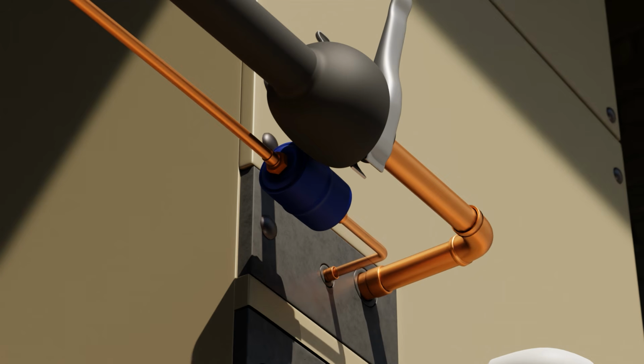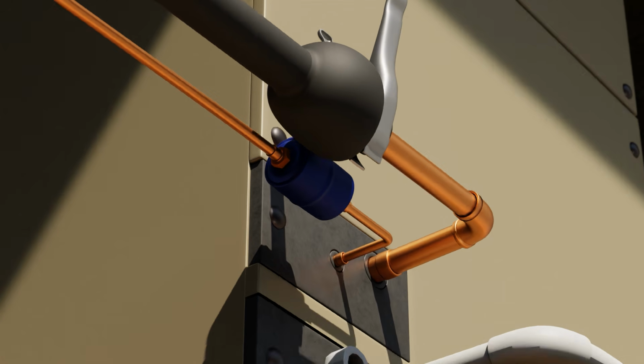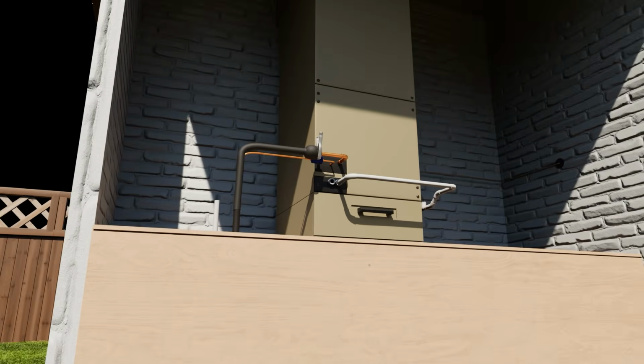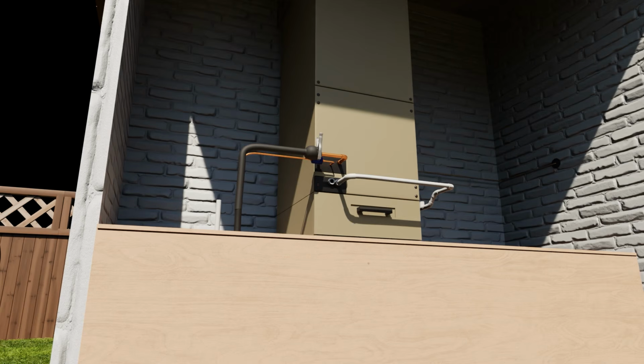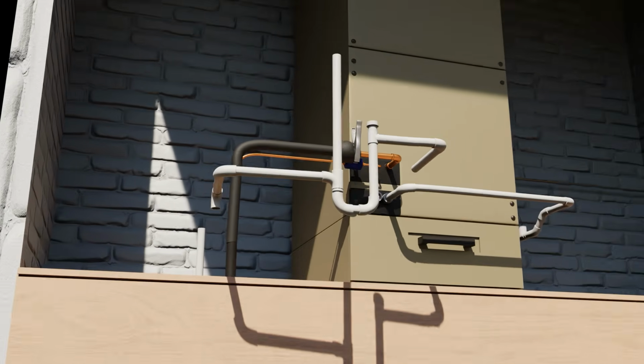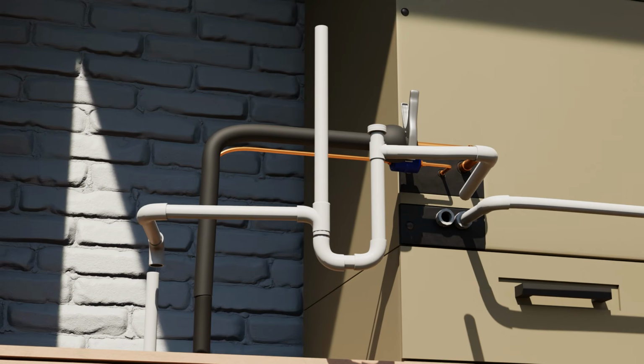We always install our liquid line filter dryer on the inside nearest to the air handler for optimal protection of the metering device and to keep the filter dryer out of the elements, which prevents rusting. Now we're going to bring in our entire drain assembly at once. As we discussed before, this indoor trap is something we really don't do in Florida, but we showed it this way because it would be a traditional setup in other markets. This is our cleanout, and this is our vent.